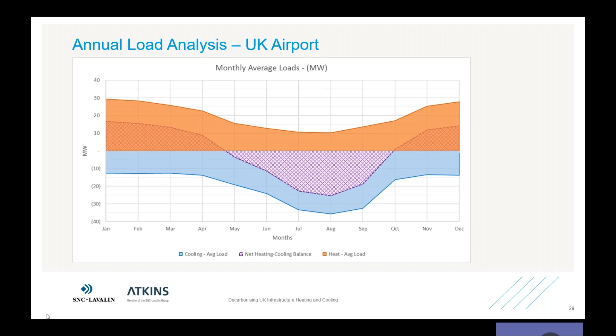What happens if we could time shift the cooling load by 3 months? What shape does that give, and what's the net resulting load across the year? And if we shifted it by 6 months, this represents the net resulting load. With perfect storage, capturing and reuse of the opposing thermal energy systems, you'd end up with a similar profile to this. It doesn't account for additional heat from heat pump operation, so it's not quite true, but it's indicative of the profile you'd end up with.